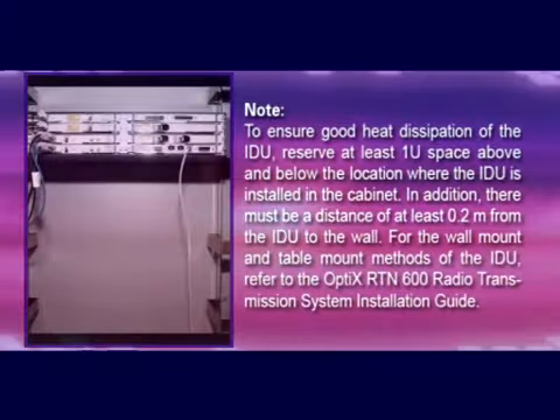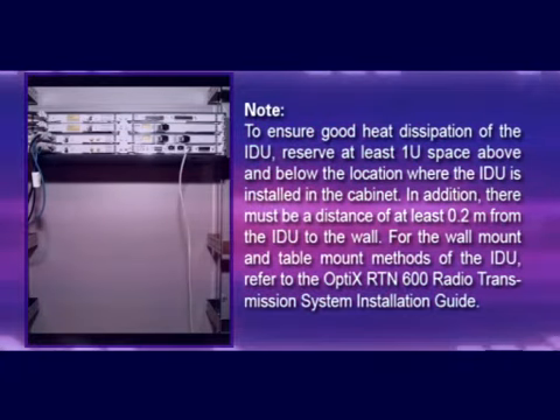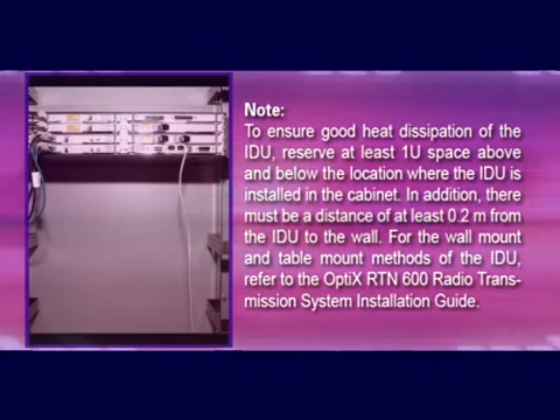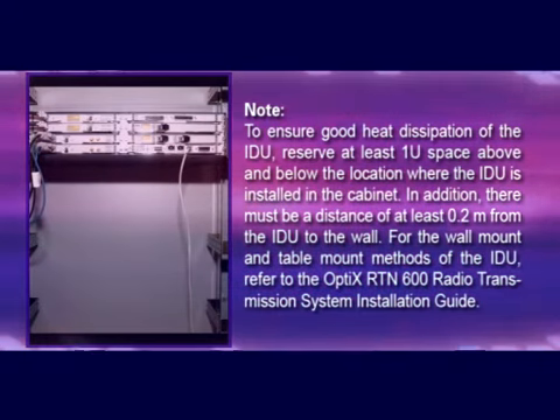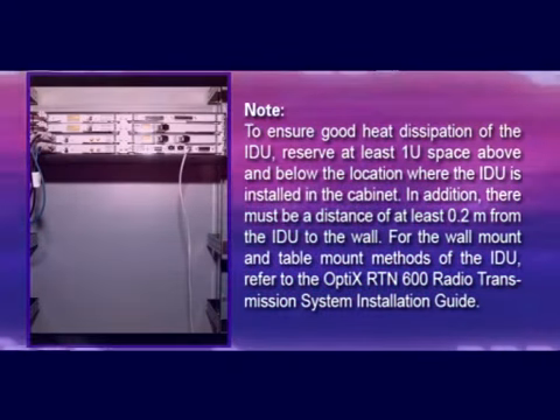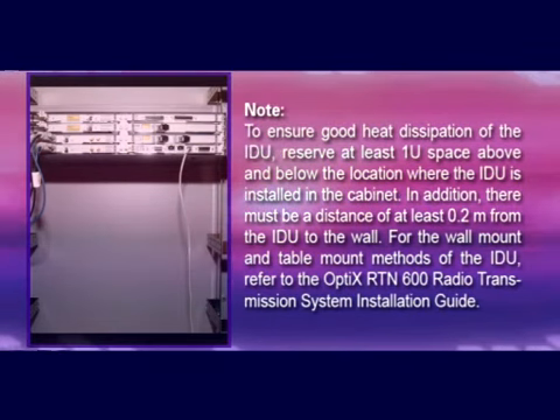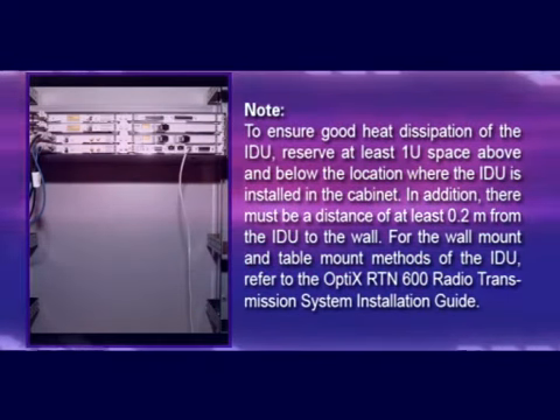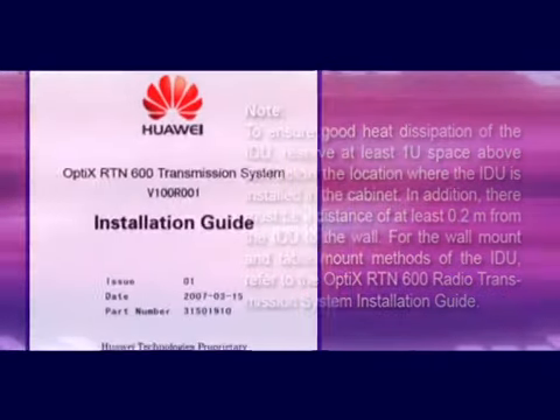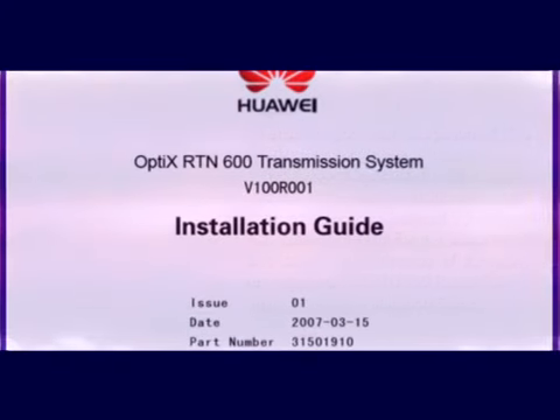Note: to ensure good heat dissipation of the IDU, reserve at least 1 unit space above and below the location where the IDU is installed in the cabinet. In addition, there must be a distance of at least 0.2 meters from the IDU to the wall. For the wall mount and table mount methods of the IDU, refer to the Optix RTN 600 Radio Transmission System Installation Guide.